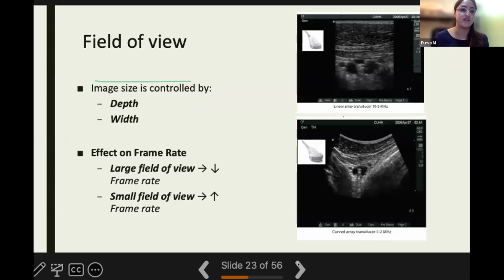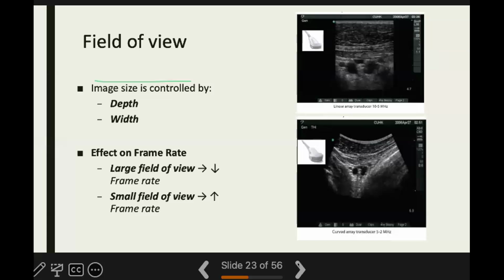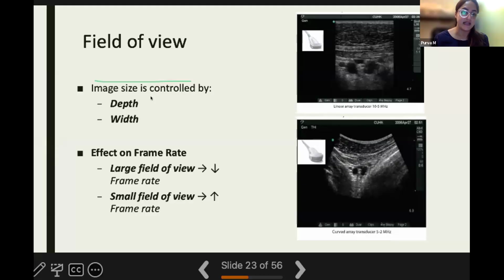The next thing that we need to touch upon is the field of view. Now that we've adjusted the depth, the gain, and the focus, we want to see if our field of view is adequate. All the structures that we wish to visualize should be present in a single field of view. The field of view is comprised of two parameters, one being the depth and one being the width. In a linear probe, we mostly have a rectangular image, while in the curvilinear, we have a trapezoidal image.